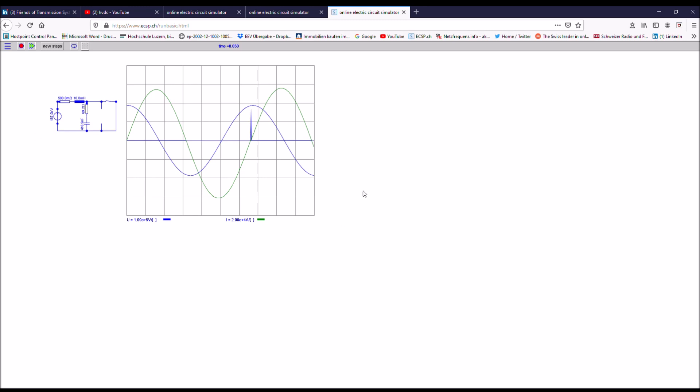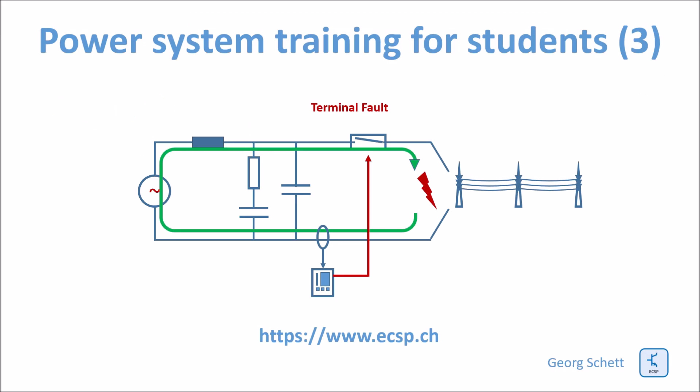You can see now that the current is just continuing to flow after the restrike. So the breaker failed. It was not able to interrupt the short circuit. So maybe it has another chance here, but otherwise, if it doesn't take this one, the breaker has failed.